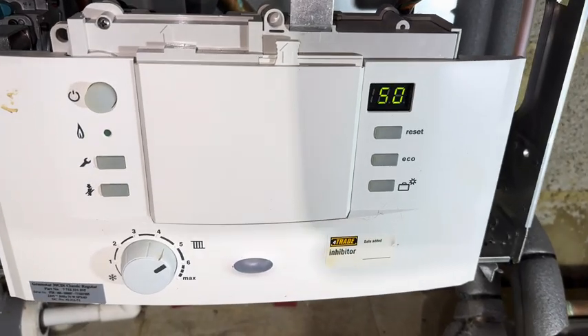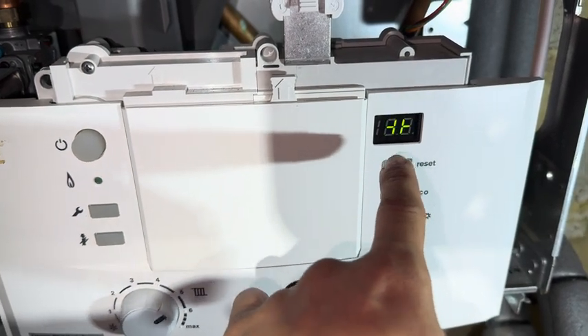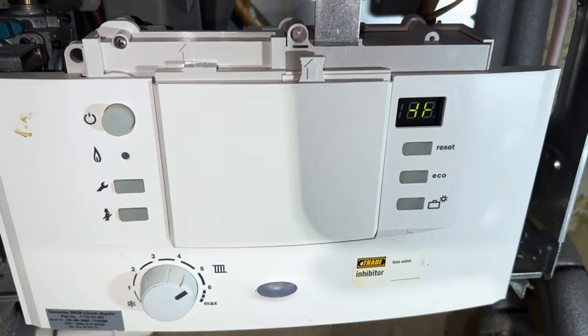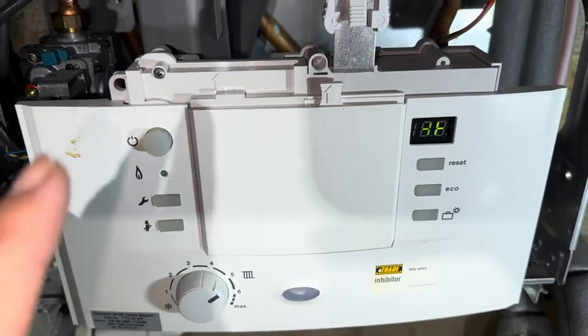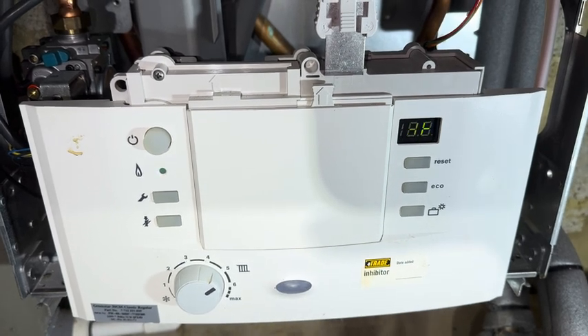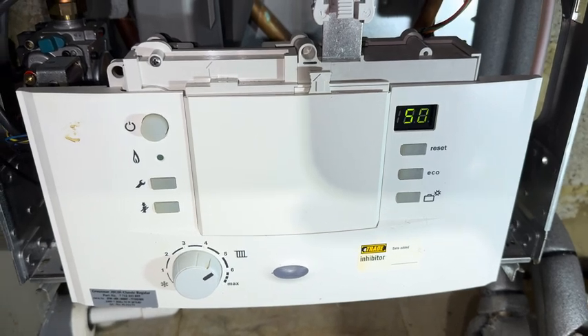This might be a handy tip for someone. You have this symbol — it's like an inverted plus or an inverted H. That's syphon fill mode and it happens any time the power is turned off to this boiler. It takes about 10 to 15 minutes before it goes into higher flame, which can be really annoying if you're under time constraints and trying to work on it.